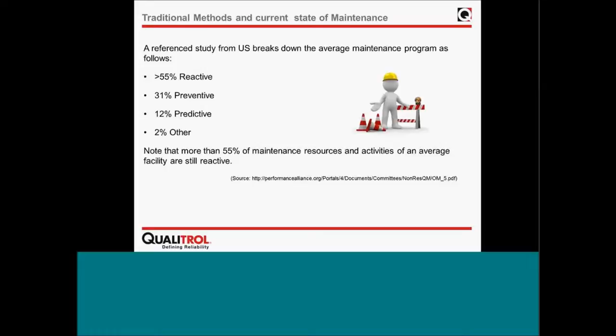But talking about high voltage equipment, transformers, GIS, most of them today will be maintained in a time-based maintenance approach. That means your equipment supplier tells you that you have to do, say, a breaker overhaul after 3,000 operations or maybe 15 years, and you follow that.